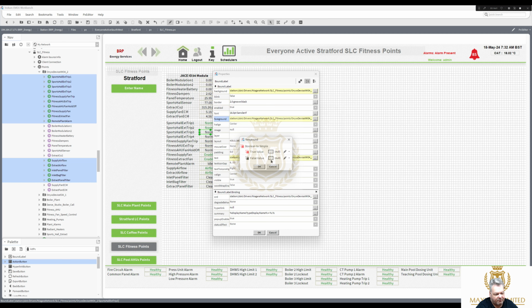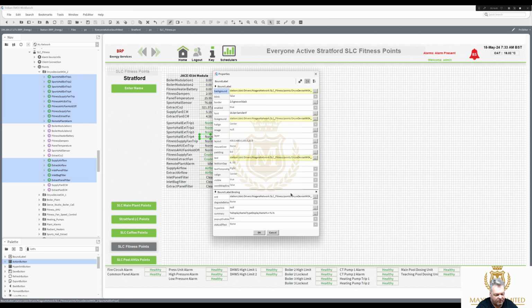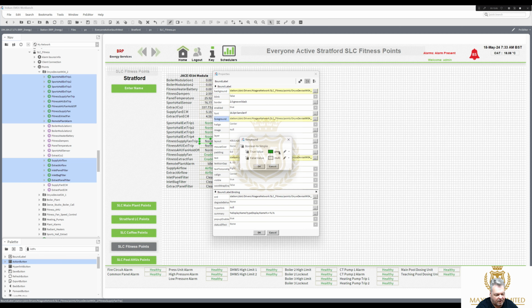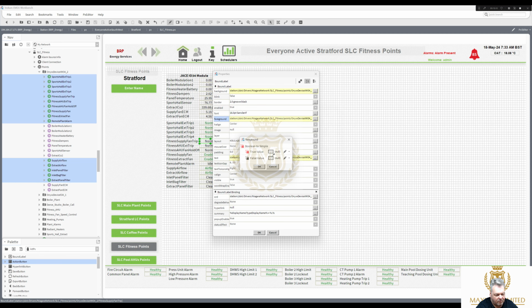Well, not the wrong way round, but it's in the logic like that, but it's not fail safe. None of this is fail safe. Normally a true being healthy is fail safe. So if anyone cuts the cable to the sensor, it will go into fault. Anyone cuts the cable to this sensor, it won't go into fault. No one will know.